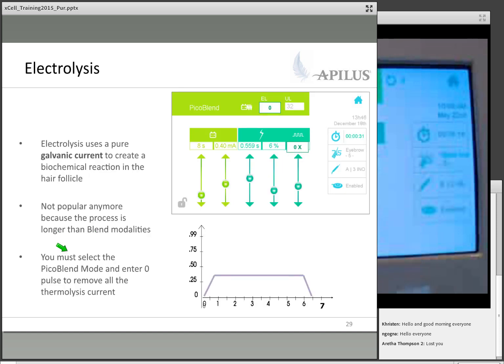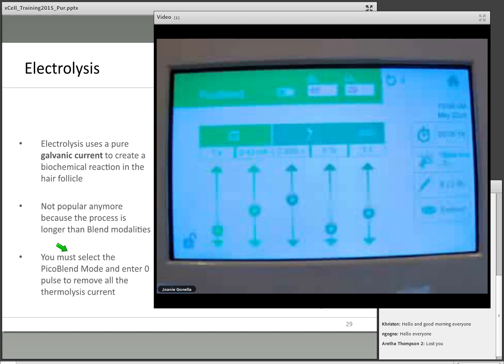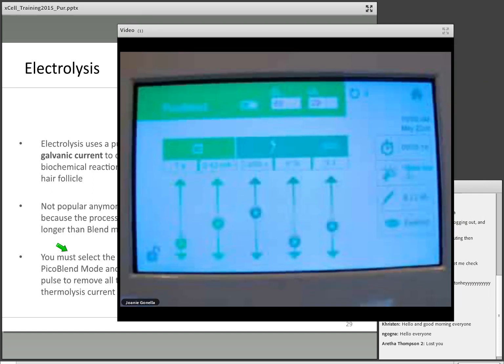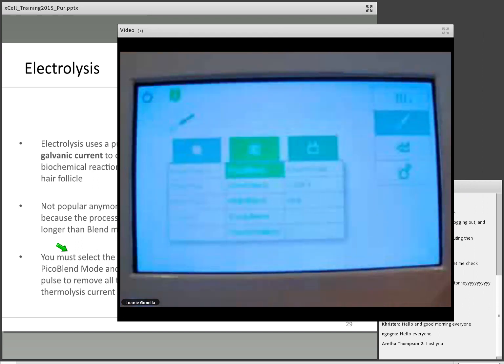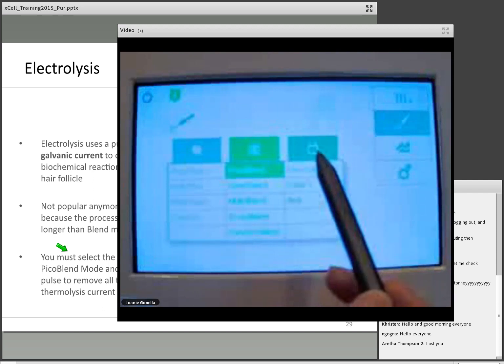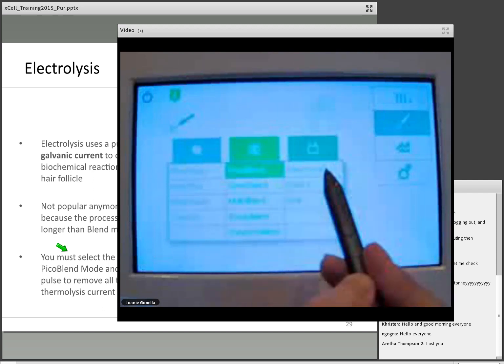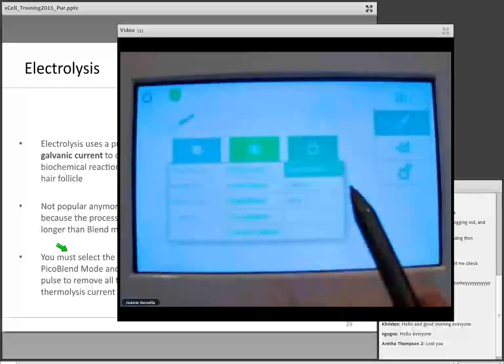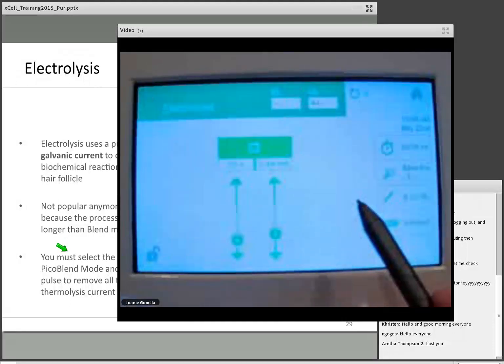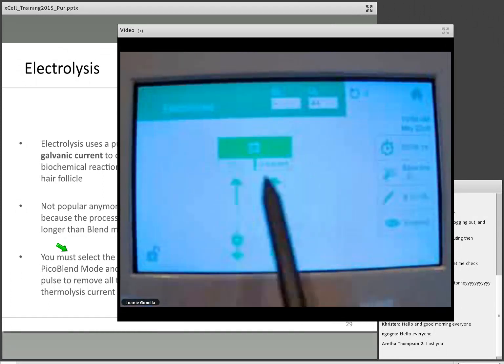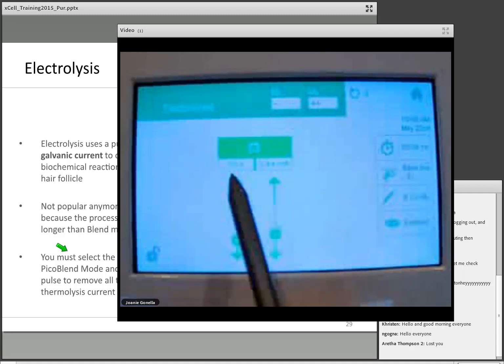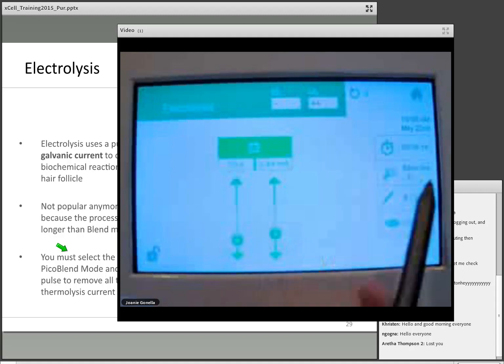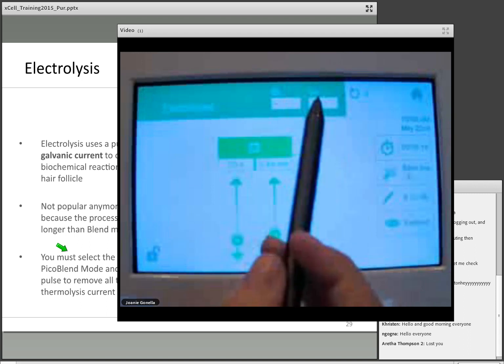The machines now come with straight galvanic. So this slide no longer applies because there's actually a straight galvanic modality, which is just galvanic current itself. So let's go back to our video and I'll show you what it looks like now. We used to have to set it, but now we'll just go home here. And underneath the third bar, this is normally cataphoresis, but it's changed now to be electrolysis, which is our straight galvanic, and then we have cataphoresis and anaphoresis. So I'll select the electrolysis, press on my scroll bars, and what I have displayed is just galvanic current. You can set this to be whatever you want. It does correlate with some of the presets anyway, and calculates the units of lye up here.